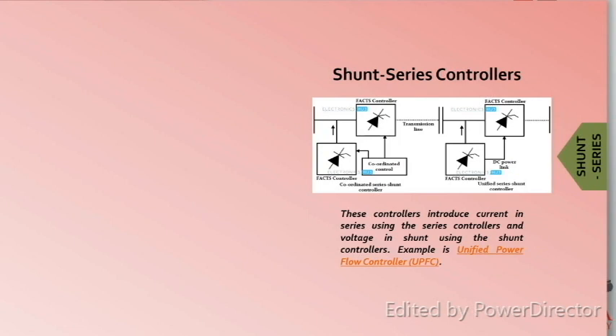The fourth type is the shunt series controllers. These controllers introduce current in series using the series controllers and voltage in shunt using the shunt controllers. Example of this type of controller is the Unified Power Flow Controller or the UPFC, which is the combination of SSSC and STATCOM without any external energy source and exhibits the characteristics of both types of controllers. It is widely used in many applications like voltage control and stability, asset optimization, line overloading limiting, angle stability, transmission cost minimization, and other more.